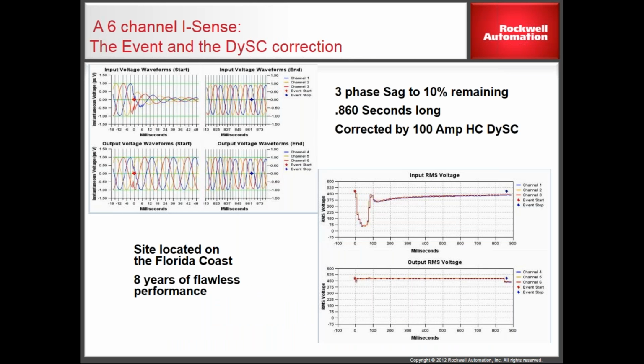This is what it looks like. So this is an actual event that's been captured using a 6-channel Isense monitor. So we had 3 channels looking at the power coming in. We have 3 channels looking at the power going out of that DySC and a single trigger. So when the event took place, this is what it looked like. And we captured the 3 cycles before the event started, then the event itself until it finally ended. This is the output of the DySC from the start to the end. And you can see the waveform, the sine wave has been reestablished through that.